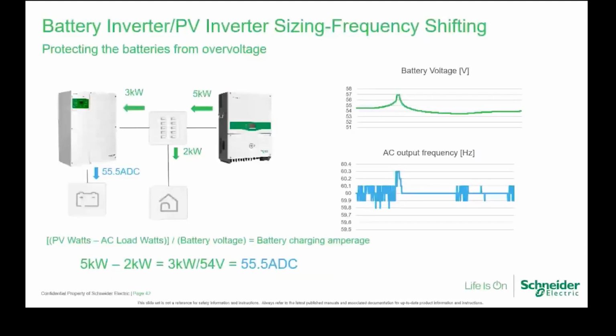Now, protecting the battery from overcharge, basically what happens with the frequency shift is that if you've got 5 kilowatts coming out of the PV inverter, but your load is only 2 kilowatts, then you have 3 kilowatts available that can go and charge your batteries. If you look at the sums, you'd have 55.5 amps DC available to charge your battery bank. However, what happens if your loads get to 5 kilowatts and the inverter is only pumping out 5 kilowatts? It means you're not going to have any available energy to charge up your batteries.